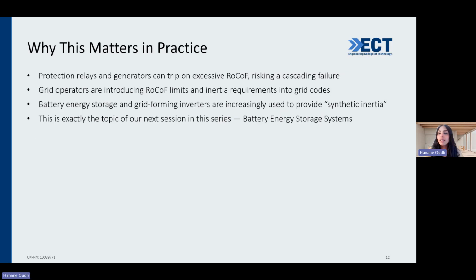So why does lower inertia matter in practice? As I said, first, protection and control systems operate based on measurement of voltage and frequency. ROCOF-based protection can operate when the measured rate of frequency change exceeds a defined threshold. The intention is to protect equipment or disconnect abnormal conditions by protection actions. These also have to be coordinated with the overall system response.